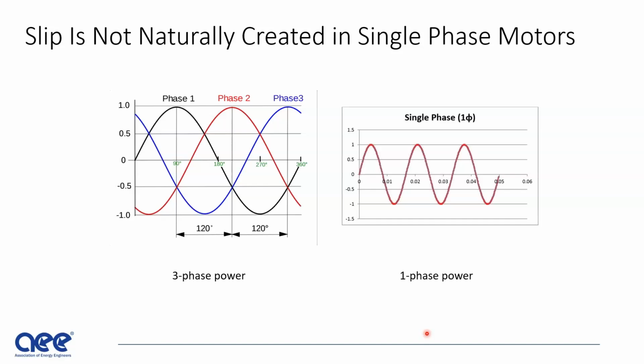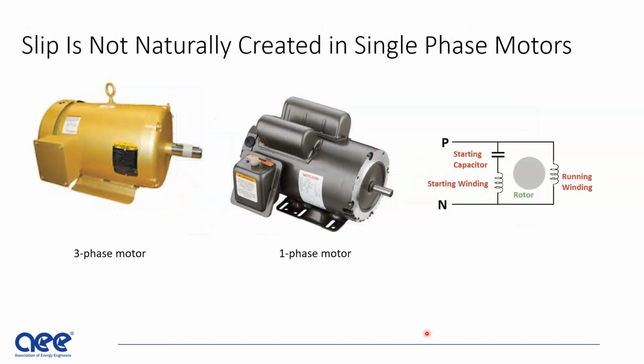Slip is not naturally created in single phase motors. So what happens is we add a capacitor, a starting capacitor, as you see right here. On single phase motors, you always see this little camel back here, and that's to create this circuit which causes a sine wave that's out of sync with the normal power sine wave, and that creates the starting torque.